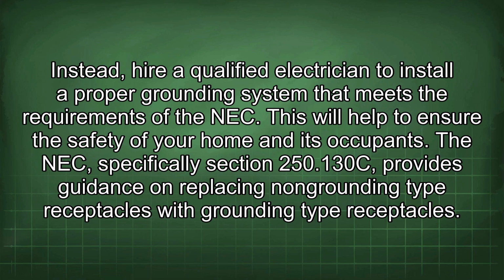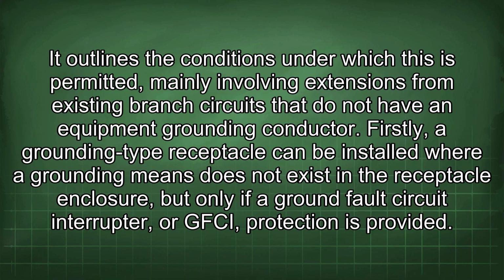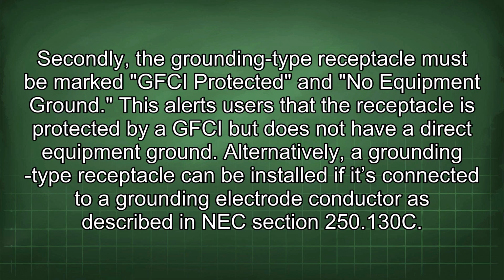The NEC, specifically Section 250.130(C), provides guidance on replacing non-grounding type receptacles with grounding type receptacles. It outlines the conditions under which this is permitted, mainly involving extensions from existing branch circuits that do not have an equipment grounding conductor. Firstly, a grounding type receptacle can be installed where grounding means does not exist in the receptacle enclosure, but only if a ground fault circuit interrupter, or GFCI, protection is provided. Secondly, the grounding type receptacle must be marked GFCI protected and no equipment ground. This alerts users that the receptacle is protected by GFCI but does not have a direct equipment ground.